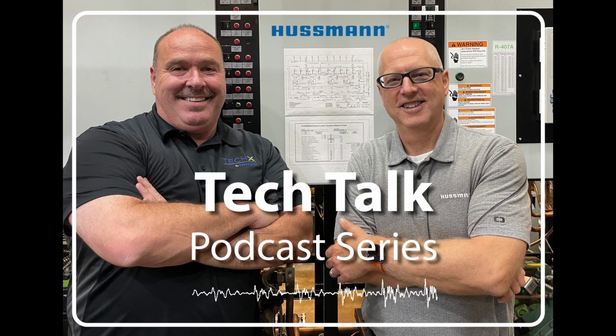So Don, let's talk for a moment just about bearing inspection and tell us a little bit about that and why that's so important. Paul, bearings on the fan shaft will need to be inspected. Grab the fan shaft, move it back and forth, and check for play in the bearings. If the fan shaft moves back and forth, this is an indication that the bearings will need to be replaced.